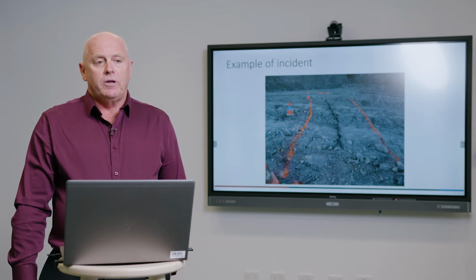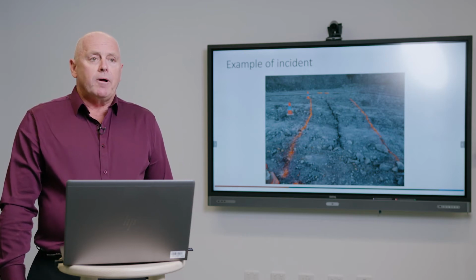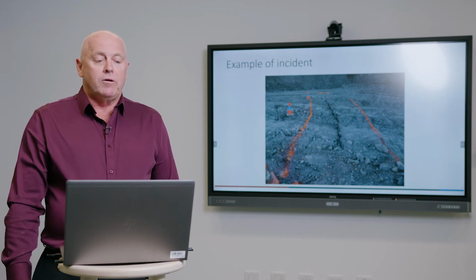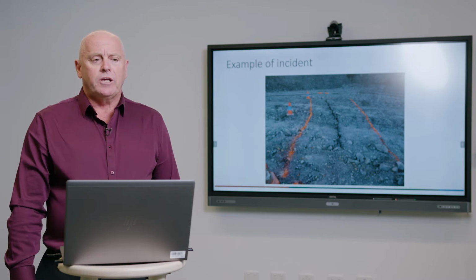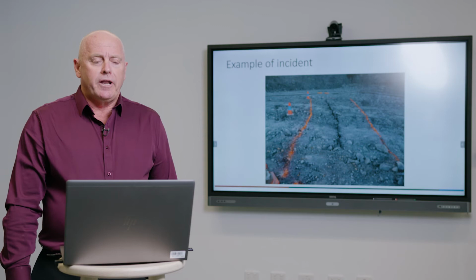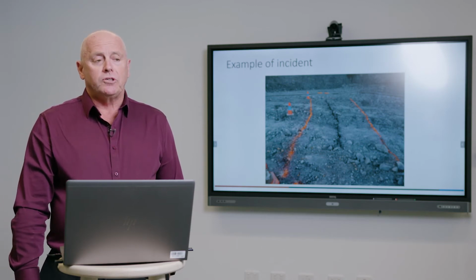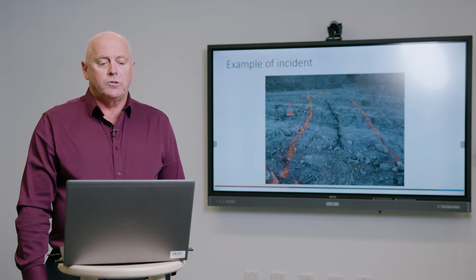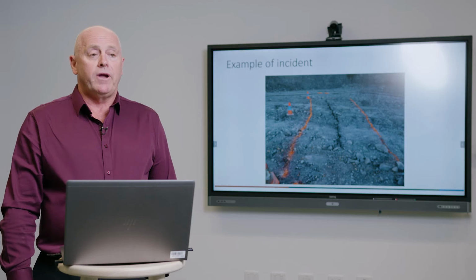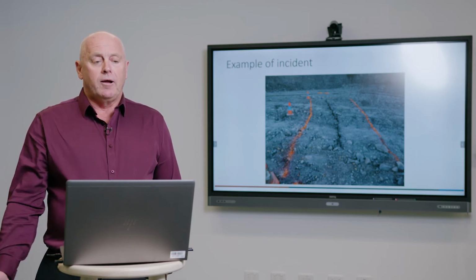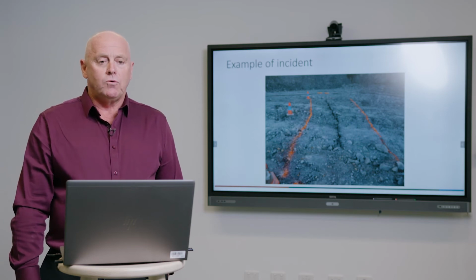An underground example I can provide is where I was working at a mine and the deputy came up to me and said that the power of the shuttle car had tripped. However, the cable was hissing, which sounded strange. So I went to the gate end box and observed that the power had tripped to the shuttle car, and then the deputy was able to show me where the cable was laying in water and was in fact hissing. So I turned the power off at the gate end box, and when I had a look at the cause, one of the phases on the vacuum contactor had actually seized in position, which was causing one phase to stay energised. Protection nowadays should have prevented this by tripping an upstream device. However, this does show that these protection systems can and do fail.